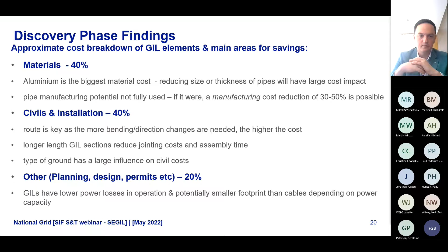About 20% identified is planning, design, permits and other benefits. GIL has lower power losses in operation than cable systems because there's less capacitance, so less reactive current is required, and it potentially has a smaller footprint than cables, especially for high capacity lines where there should be 3, 4 or 6 cable circuits installed next to each other.